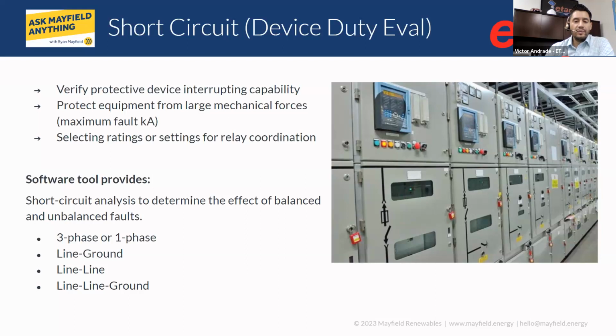They are already used to this because industrial and commercial users ask for this information all the time. But that's also important to know, because in the event that we have a fault on the main substation, right, we're going to be getting contribution from not just the PV and the inverters, but we're also going to be getting a huge amount of contribution coming from the utility. So we add up both sources of contribution, and we arrive to the maximum available fault. And that's what we need to compare against the interrupting rating of the main protective device, or gear in this case, for example.